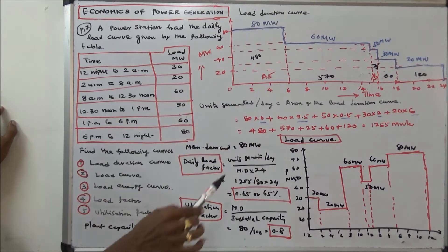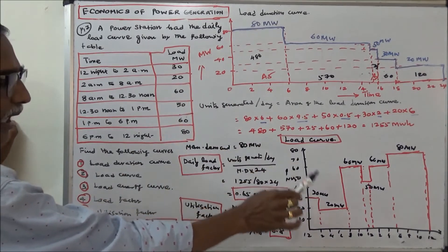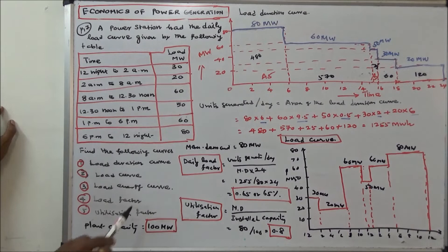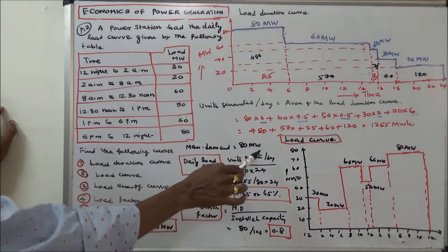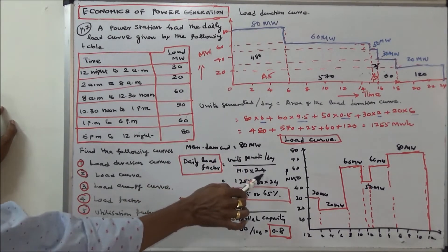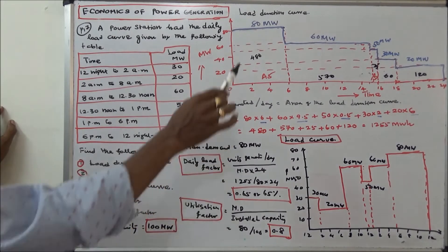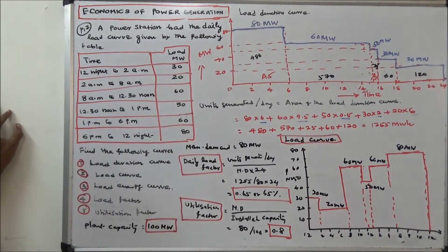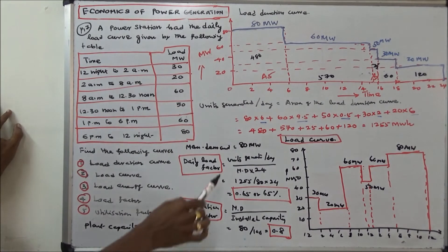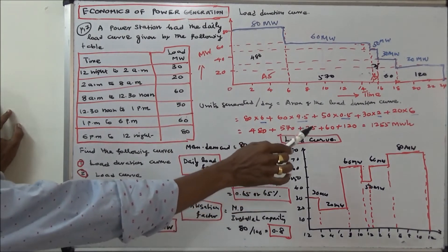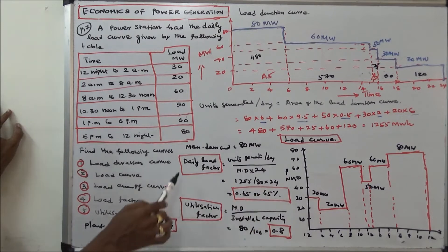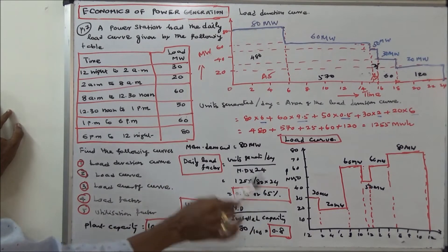Next we draw the load curve. The next question is to calculate the load factor. Daily load factor equals units generated per day divided by maximum demand times 24. From the load duration curve, the maximum demand is 80 megawatts. Units generated per day is 1255 divided by 80 times 24. Daily load factor equals 0.65, or 65%.